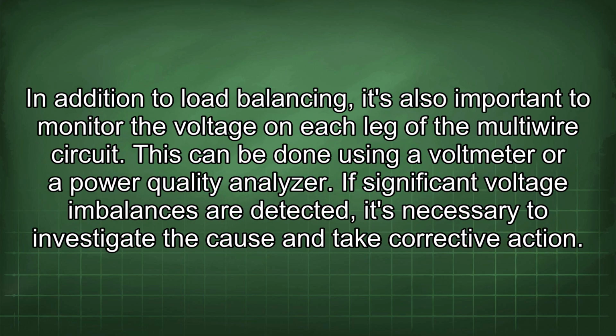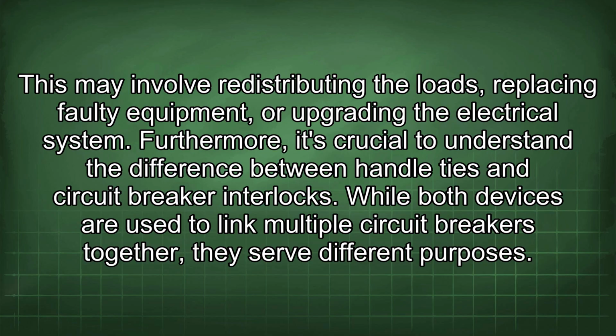In addition to load balancing, it's also important to monitor the voltage on each leg of the multi-wire circuit. This can be done using a voltmeter or a power quality analyzer. If significant voltage imbalances are detected, it's necessary to investigate the cause and take corrective action. This may involve redistributing the loads, replacing faulty equipment, or upgrading the electrical system.